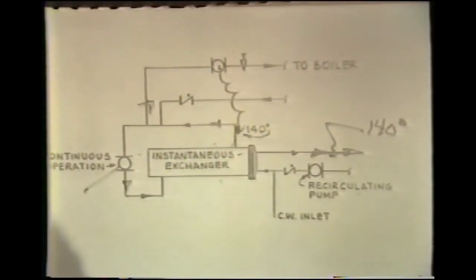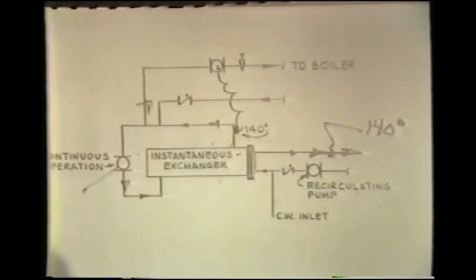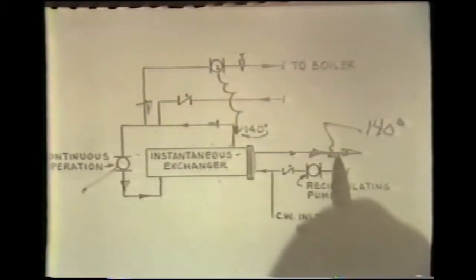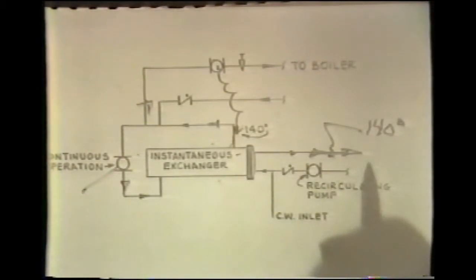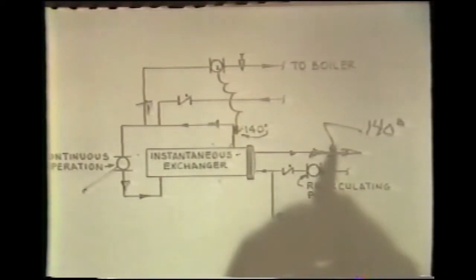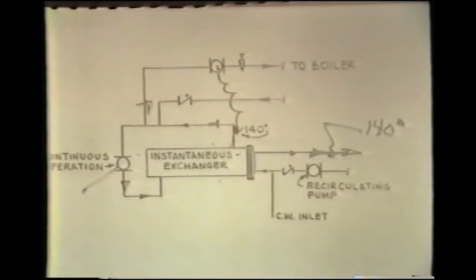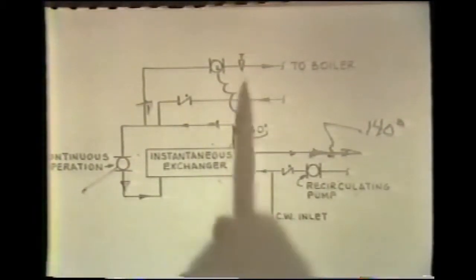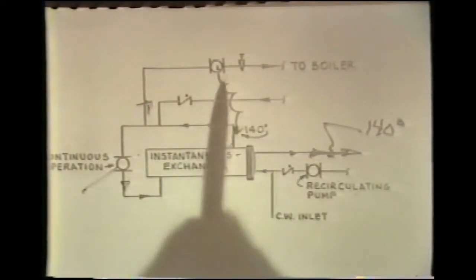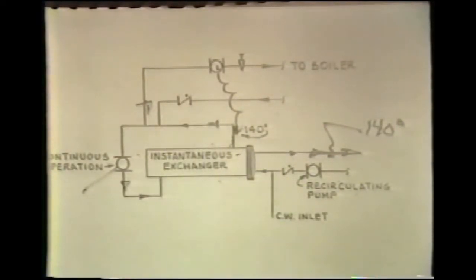This has been used for a great many years in this area and again was basically established because of problems associated with conventional control in which the water temperature leaving the exchanger was very high, it fluctuated widely, and did indeed cause some troubles with people in showers getting scalded and having problems such as that. This solved the problem, but is indicative of the close control that can be achieved by injection pump operation.